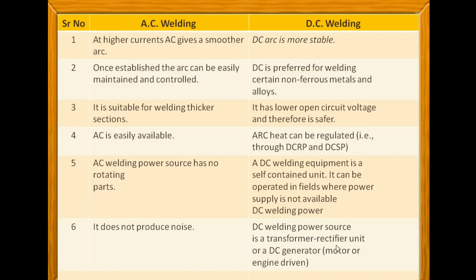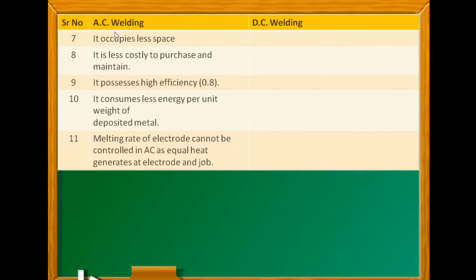DC power source can be a DC generator, motor, or engine-driven unit. In the case of AC welding, it occupies less space; DC takes up more space. AC is less costly to purchase and maintain, and it possesses high efficiency up to 80 percent. It consumes less energy per unit weight of deposited metal. The melting rate of the electrode cannot be controlled in AC, as equal heat is generated at the electrode and the job.